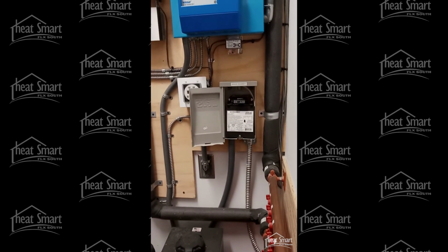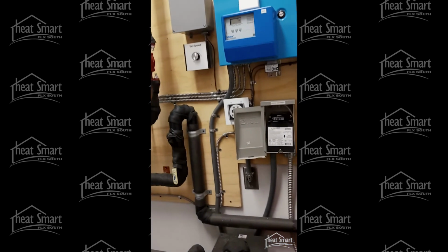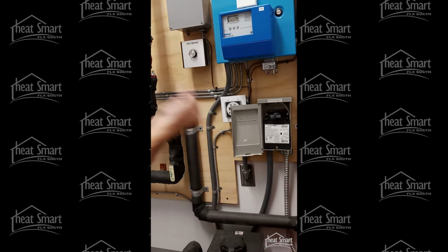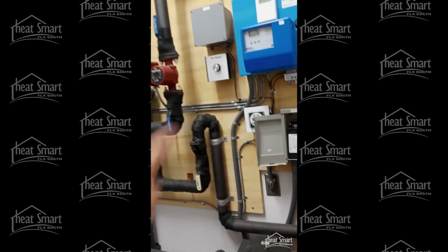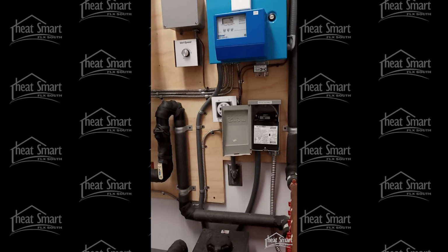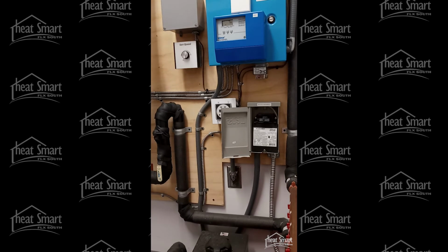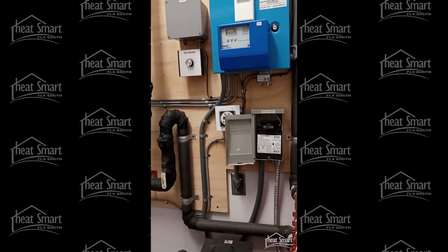So it's a service disconnect. The reason this is here is if a service technician has to work on the system, he or she can just pop that right out, which kills the system. They don't have to chase it to the breaker, which isn't a big deal because the breaker's right over there. But this is a code requirement. Any of these heat pump type systems on dedicated circuits are supposed to have AC disconnects like this.